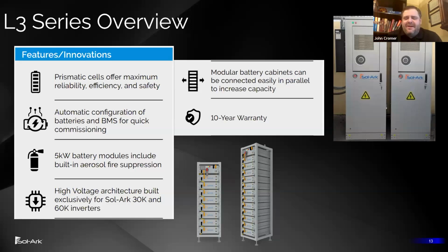Whenever you have a potential for a water leak in a system, whether that's liquid cooling or fire suppression, those safety features can also be failure points that are no longer safety features. If they fail, they can cause arc faults, and we see that in industry all the time. And so for this, maybe for containerized solutions, you need that level of sophistication.